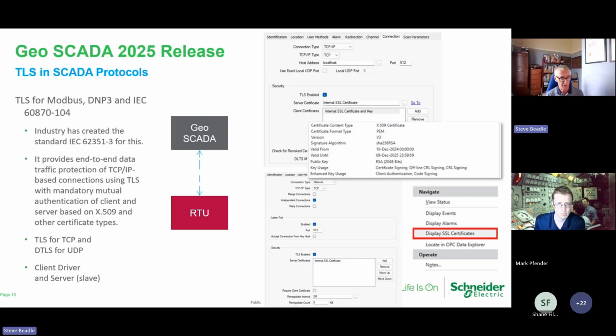But TLS for SCADA protocols could work both ways. So not only can it be used by the SCADA master or central system to confirm the identity of the RTU, it could be used the other way around as well. And in fact, this might be a stronger use case for the RTU to confirm the identity of the SCADA server, so that it accepts controls, software downloads, and other configuration only from the correct master station and not from any rogue master impersonating the master.